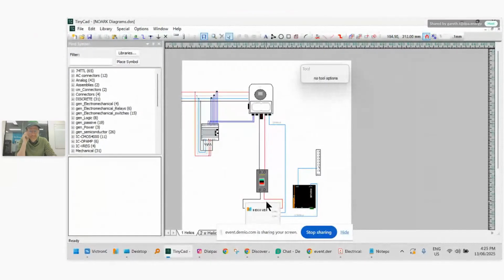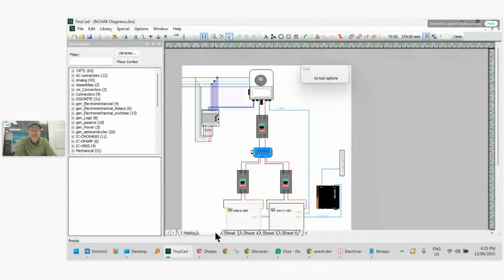Okay, so if the inverter is less than 2 meters from the battery, you only need to use a single 2-pole breaker. And so that can cover the inverter and the battery. That's in the scenario where you have 1 battery and 1 inverter. Once you have 2 batteries, you're going to need to have a breaker on each battery. But if it was less than 2 meters away, you wouldn't need this inverter one, because your shutdown procedure can just be turn off this one and turn off that one. But if it was more than 2 meters away, you're going to have 1 on each breaker, go into your bus bar, and then another one into the inverter.